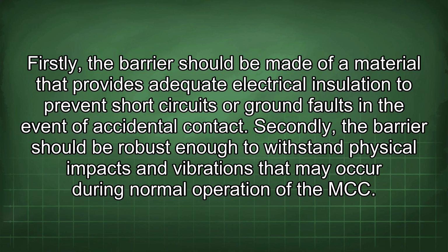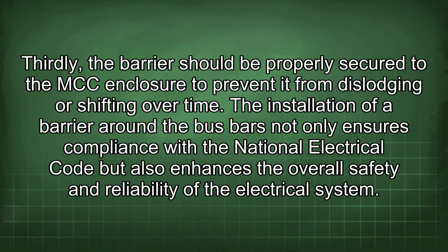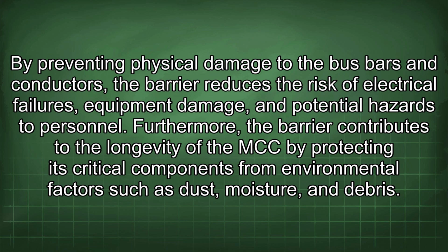Secondly, the barrier should be robust enough to withstand physical impacts and vibrations that may occur during normal operation of the MCC. Thirdly, the barrier should be properly secured to the MCC enclosure to prevent it from dislodging or shifting over time. The installation of a barrier around the bus bars not only ensures compliance with the National Electrical Code but also enhances the overall safety and reliability of the electrical system. By preventing physical damage to the bus bars and conductors, the barrier reduces the risk of electrical failures, equipment damage, and potential hazards to personnel.